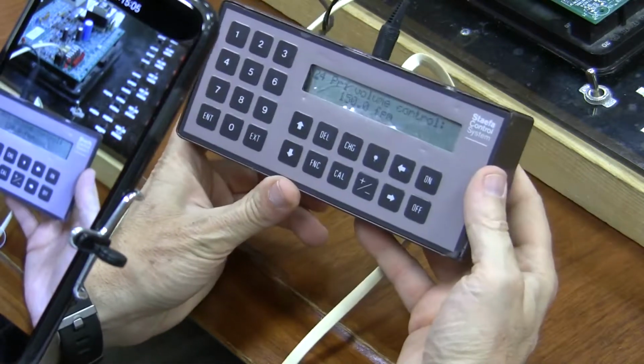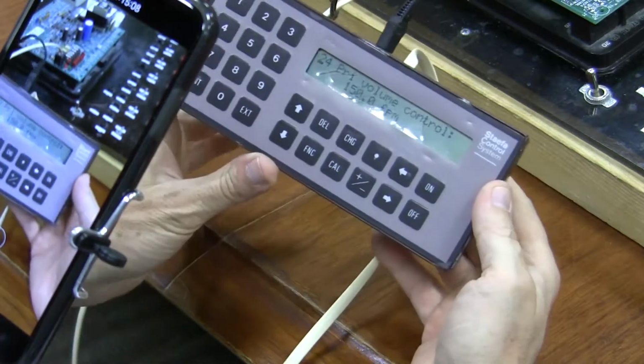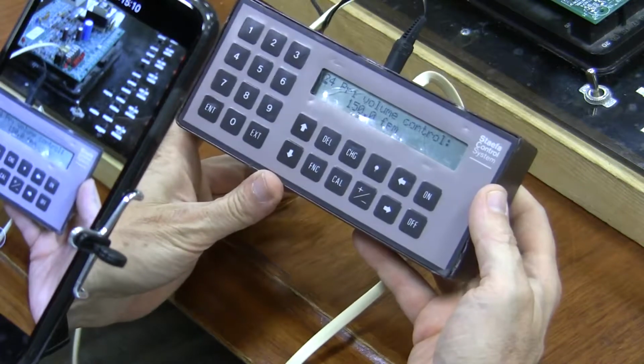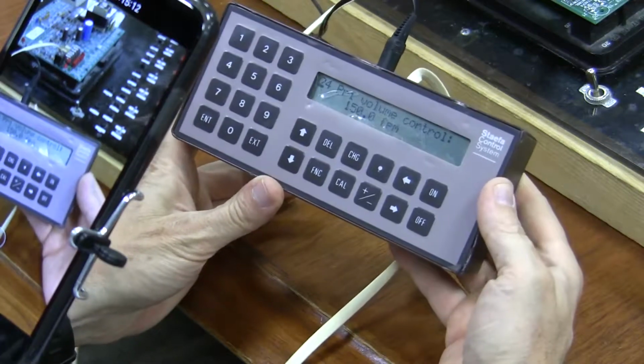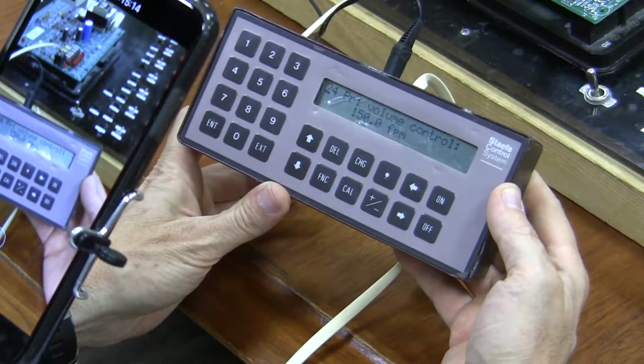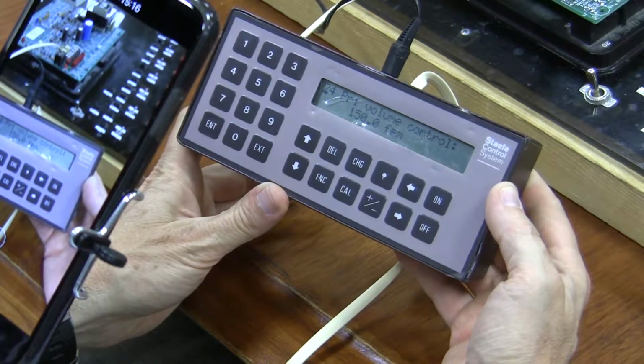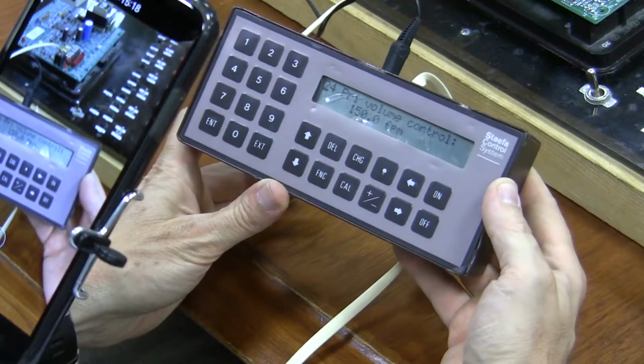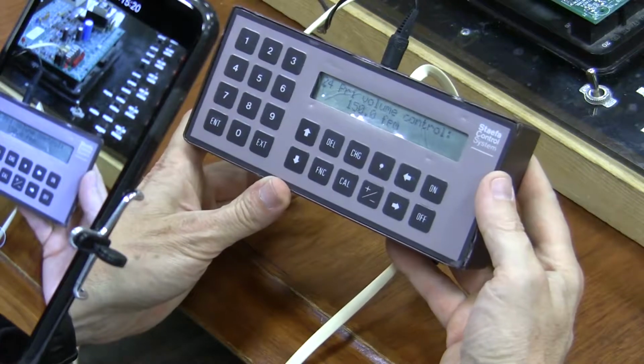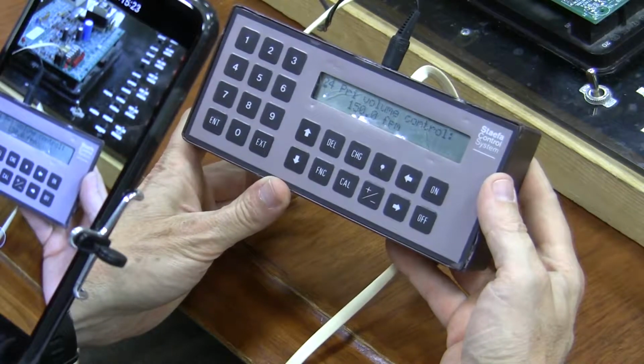Now this one here is really important, parameter number 24, because this one is telling me what, after all my calculation, this is telling me what my VAV box is trying to obtain in terms of flow. He's trying to obtain 150 feet per minute in this particular case.